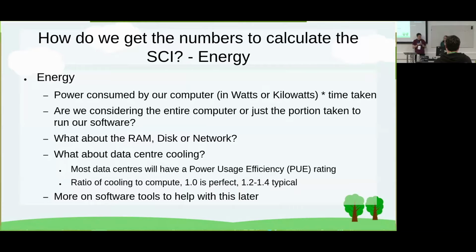And I do worry slightly that some of the commercial providers might try and do that as a way of greenwashing themselves. I think Loic wants to say something as well. They're already doing it. Already using it, already greenwashing over it. So the PUE that's reported is usually the design one. When they build a data center, that's the ideal PUE, and that takes into account any kind of mitigation measure, like plugging the heat exhaust to the swimming pool or whatever. It's also different from the actual PUE, which depends on how much equipment is in there. So they're already accounting for it, probably too much, but it can help.